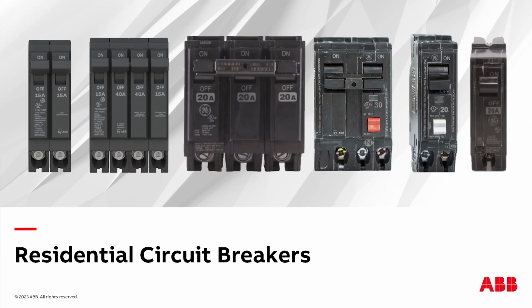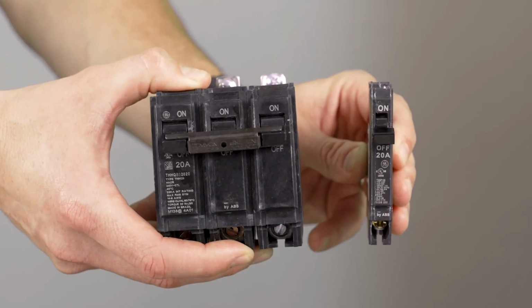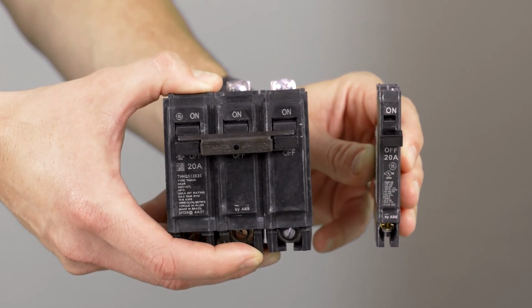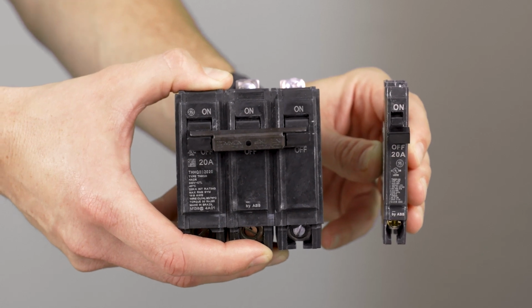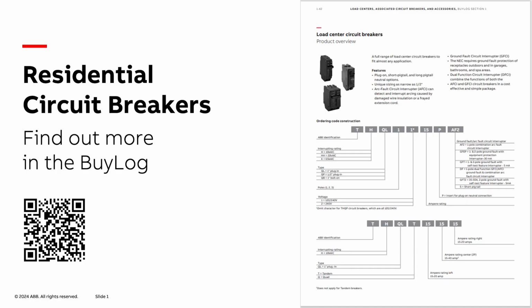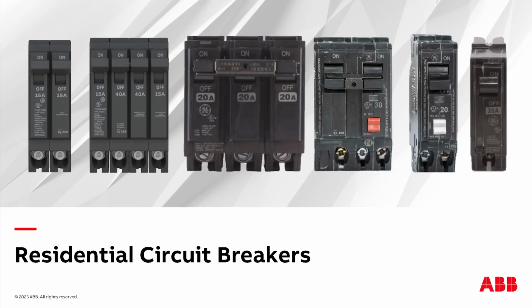So ABB has many options available for miniature circuit breakers for both residential and commercial applications. Our frame sizes range from 1/2 inch to 3 inches depending on the type of breaker. Also, whether it's 1 pole, 2 poles, or 3 poles. The amperage range can also be from 15 to 125 amps with short circuit ratings available from 10,000 AIC to 65,000 AIC. ABB's miniature circuit breakers have tin or silver-plated copper stabs for corrosion resistance with a heat-resistant thermoset case. The ABB BuyLog is a great place to confirm the miniature circuit breaker options required for your application.